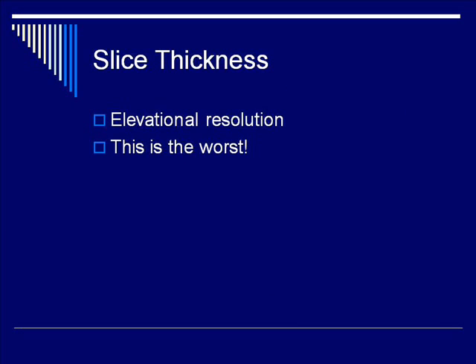Finally, let's talk about slice thickness resolution, also known as elevational resolution. This is consistently the worst resolution. Recall that we can usually only adjust focus using an array and electronic focusing techniques, and we use one horizontal row of piezoelectric elements to do this focusing. That gives us relatively good control of focus in the axial and horizontal directions. However, as there are no elements at different elevations, we cannot do anything about slice thickness. This one is also significantly more complicated to measure, as you can see starting in the next slide.